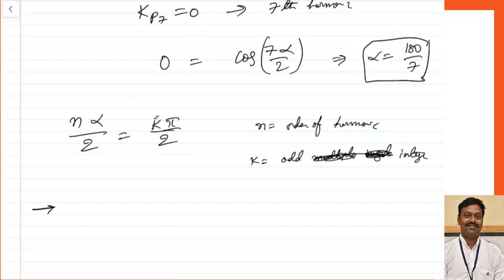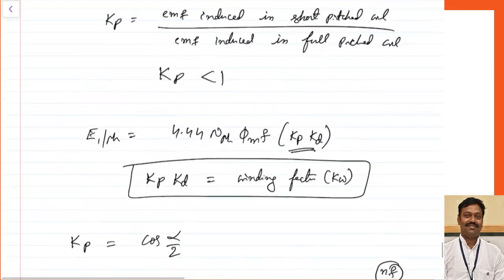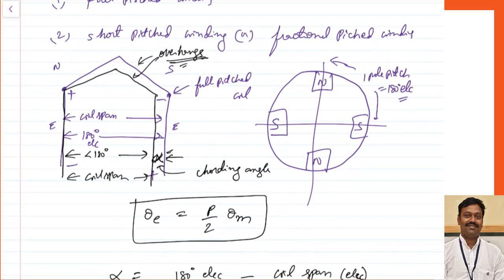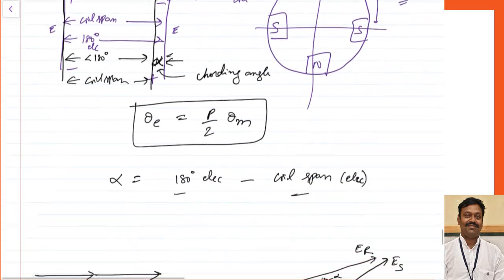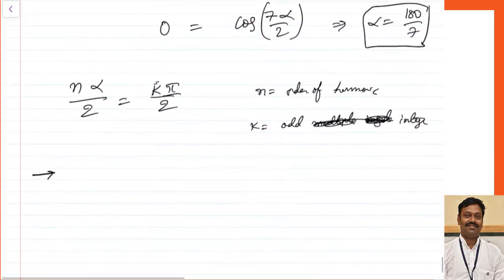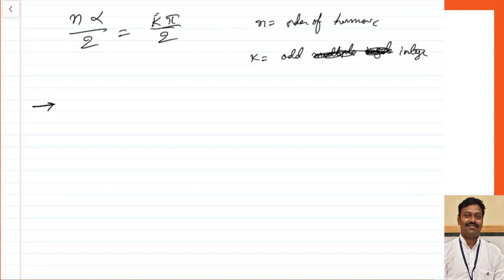There is an advantage of employing the short pitched coil: winding overhangs are decreased. It is observed practically that the amount of conductor saved due to decreasing winding overhangs dominates the extra turns required to compensate for the decrease in EMF. That means a short pitched coil requires less copper than a full pitched coil. Additionally, as winding overhangs decrease, the flux linking with those overhangs — which is useless — decreases, automatically improving the efficiency of the system.